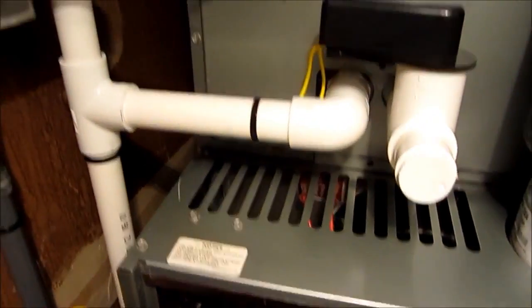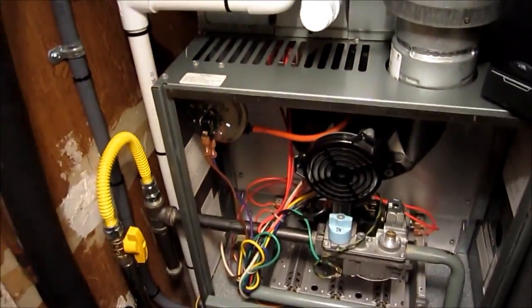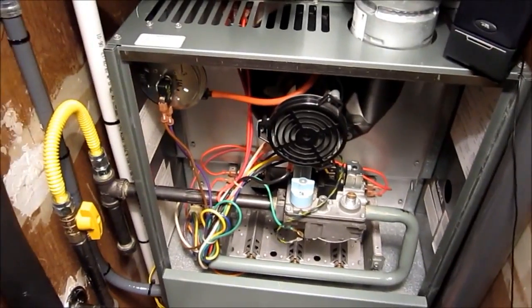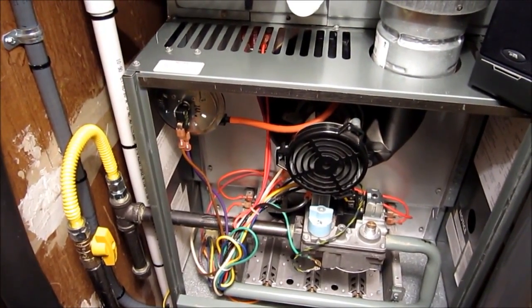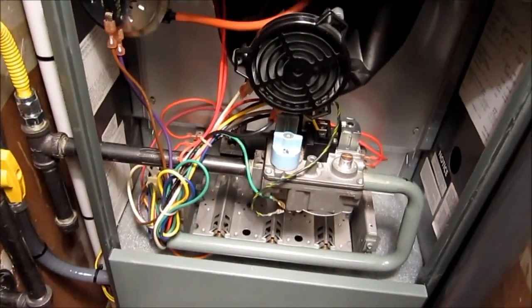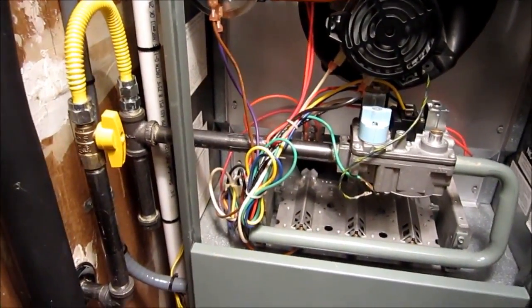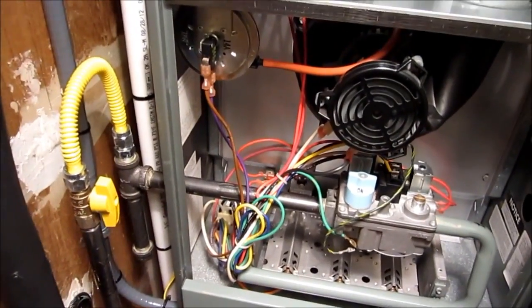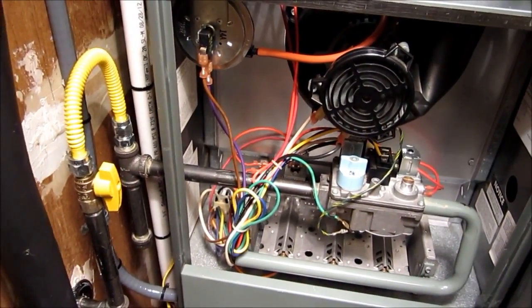Let's turn it off for the entire controller. Okay Ray, we're good right there, brother. What we actually did was we checked for 24 volts in each terminal. This indicates whether or not the switch is open or the switch is closed. If we've got 24 volts, it indicates that our switch is closed. If we had voltage present on one terminal but not the other, it would mean the switch is open.